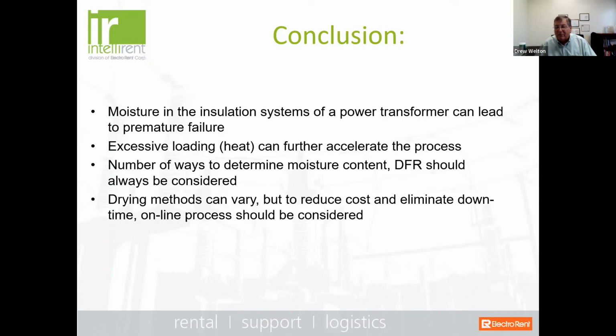Passed the factory acceptance test, even passed it after they tried to do a repair on it. But somewhere in that tank was a loose ground strap or something, causing that arcing and sparking to cause an issue in the transformer itself. So yeah, a lot of times some of the bad manufacturing isn't always visible until you actually have a continuous load.